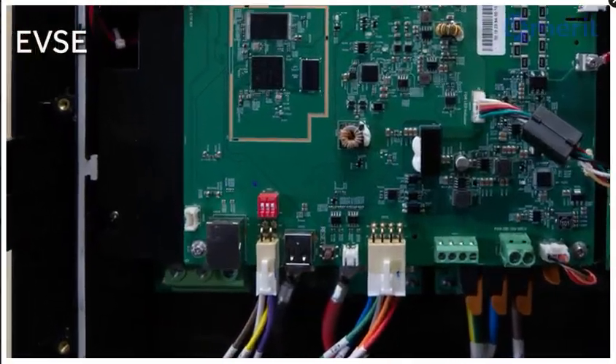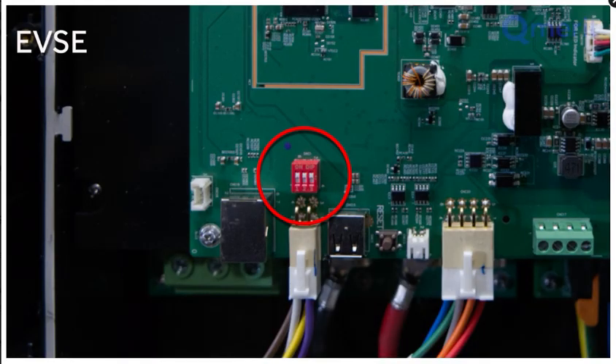On the EVSE, this is the dip switch controller to set the amperage of the charger. Currently, it is set to 80 amps. The only time you'll need to adjust this is when derating the charger.